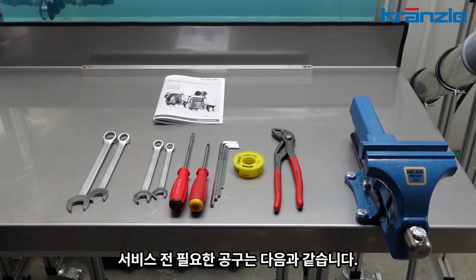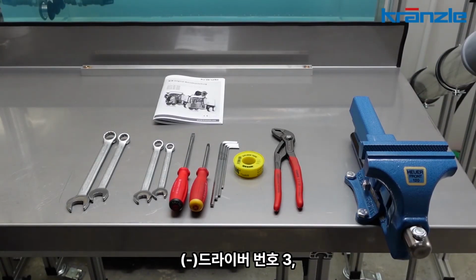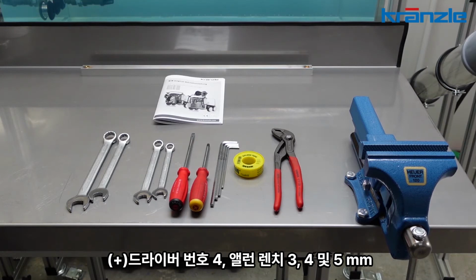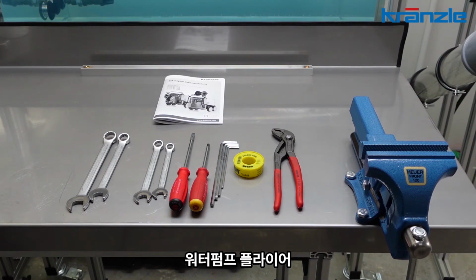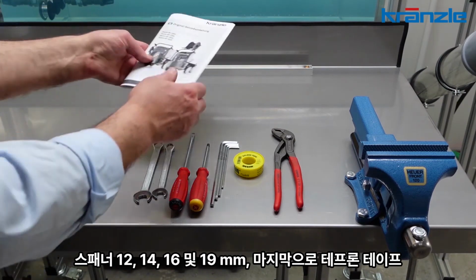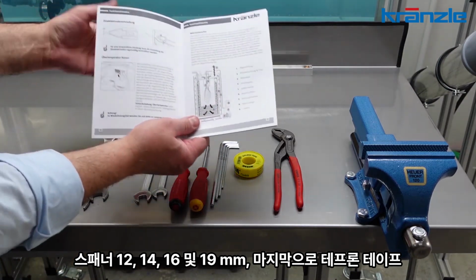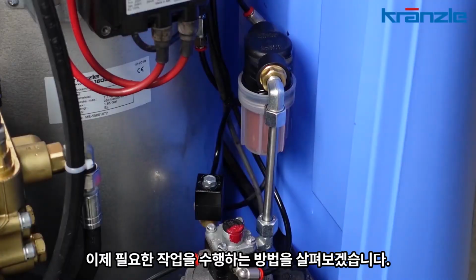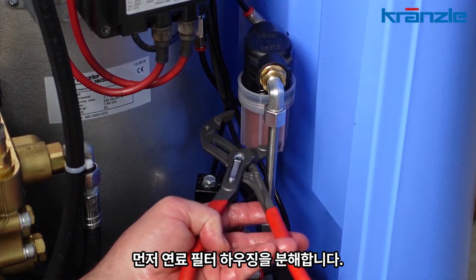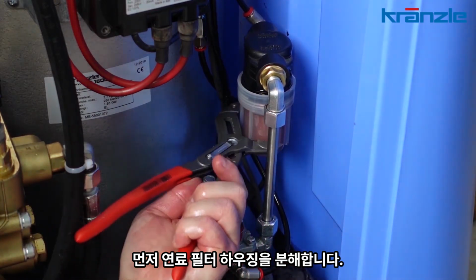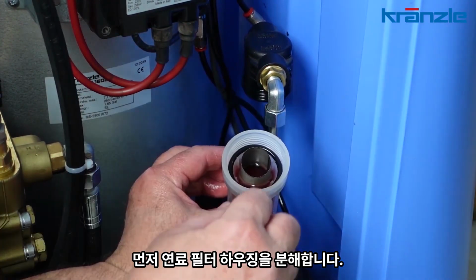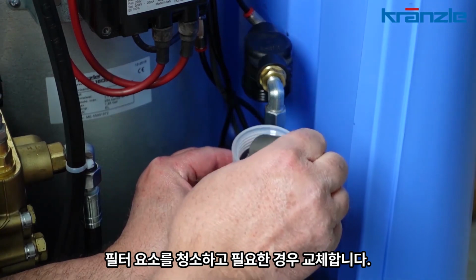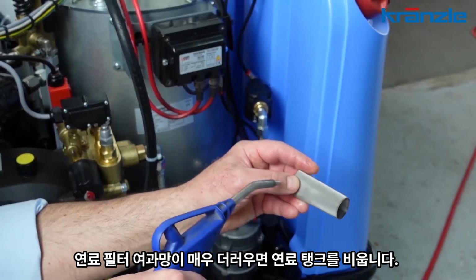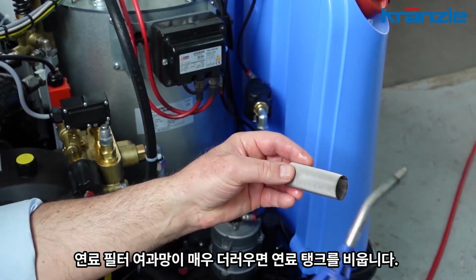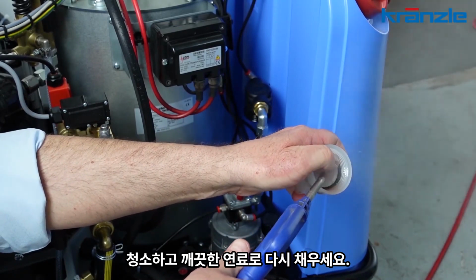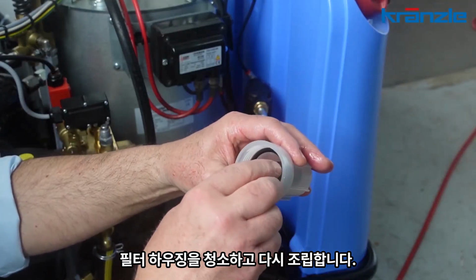The following material will be needed prior to service: a screwdriver number 3, Phillips screwdriver number 4, Allen wrenches 3, 4, and 5 mm, water pump pliers, box wrenches 12, 14, 16, and 19 mm, and lastly, Teflon tape. Now, let's see how to perform the necessary work. First, disassemble the fuel filter housing, clean the filter element, and replace it if necessary. If the filter screen is very dirty, empty the fuel tank, clean it, and refill it with clean fuel. Clean the filter housing and reassemble it.